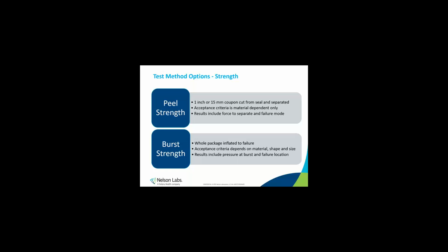Both methods have some options in the standard, and if you're comparing data, like if you're checking to a manufacturer spec or comparing data from 2 labs, you need to use the same test options to get an accurate comparison. For a peel test, you cut a coupon from the seal. The coupon width depends on the standard you're following. The coupon's placed on a tensile tester and peeled apart to measure the peel force. Once you have acceptance criteria for one type of pouch, you can use that same minimum value on different sized versions of the same pouch, since the peel force is normalized by testing a coupon.